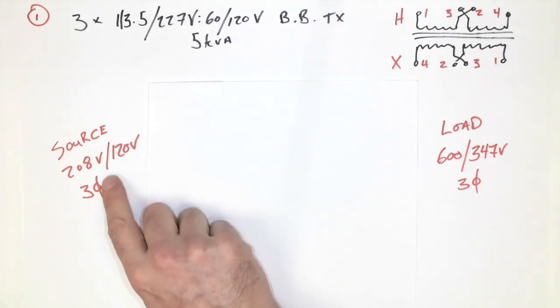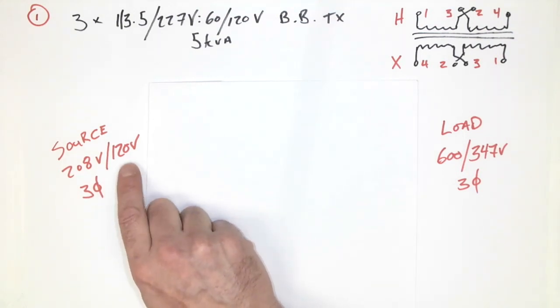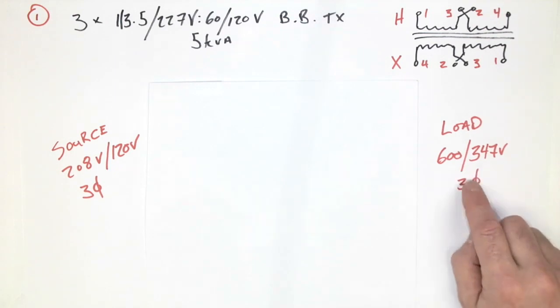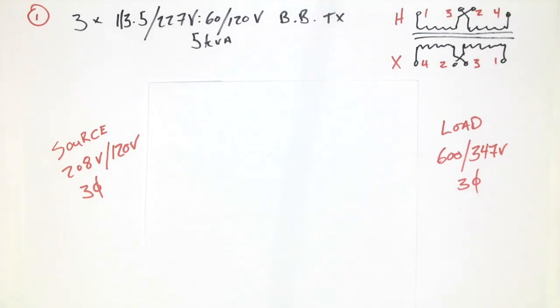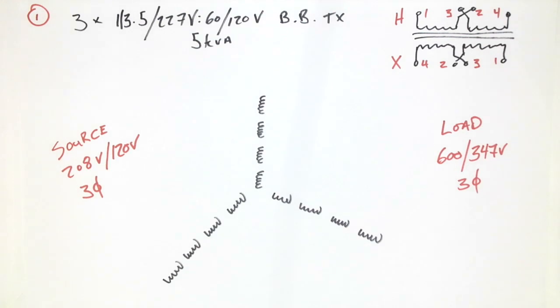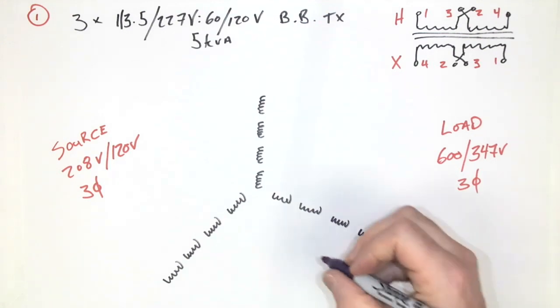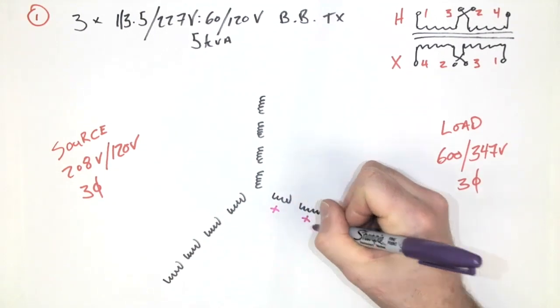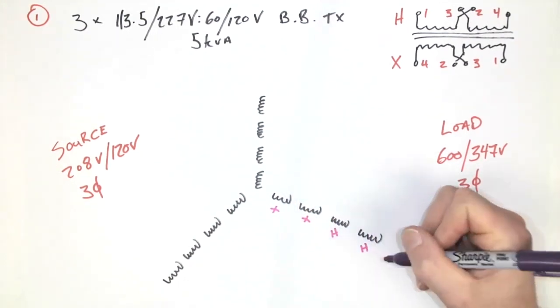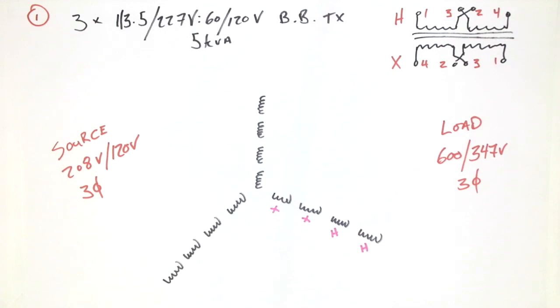Now we've got a source of 208 volt line, 120 volt phase, and a load of 600 volt, 347 volt phase, and that's three phase. We're going to do a Y connection, which means we should arrange our windings for the individual three transformers, something like this, so that we can start to have context for where the different values are going to be. Now, for my installation here, I'm going to choose to put the X windings here and the H windings here, and you'll see why that is as we go along.